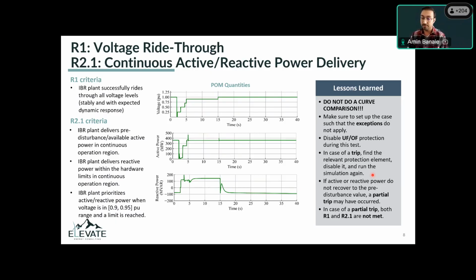The other one is that if active or reactive power do not recover, a partial trip may have happened. So be careful with that. And that's also a violation of R1 and R2.1, since these 2 requirements want active power to recover to the pre-disturbance value.